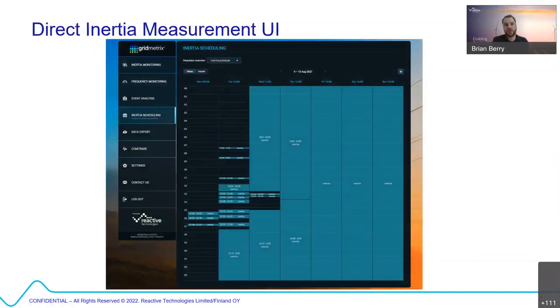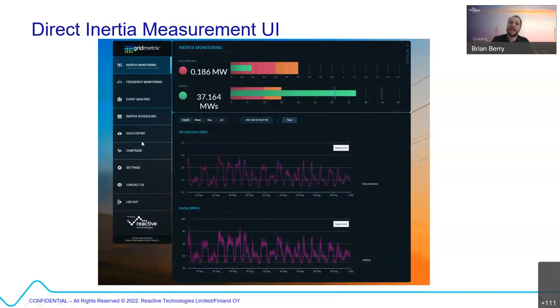So talking about our solution a little bit more, I just want to give you an idea of how this actually works. Because we are creating a power disturbance, you can actually schedule inertia measurements. You don't have to wait for an event or build up some sort of artificial intelligence. You literally can say, okay, tomorrow I want to run from midnight through to 1 o'clock. I want to get a continuous stream of inertia. And that's how our system basically works. And at the end of the day, what that schedule produces is then a trend of inertia. So just to give you an idea of that solution.